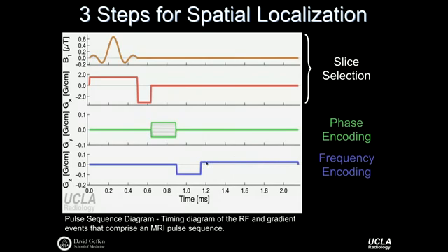This relatively low amplitude gradient that's constant for, in MR terms, a relatively long period of time, is essential for helping us form the echo, but also doing the spatial frequency encoding. We'll dig into this.